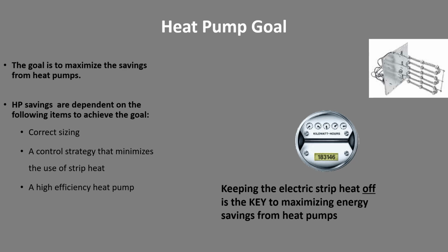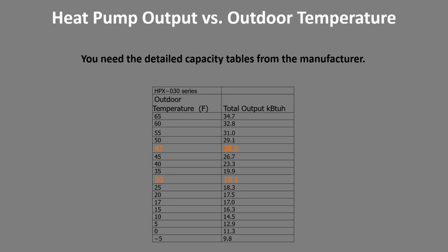The goal of installing heat pumps in the PTCS program is to keep the electric strip heat off. Let's just say we install a 3-ton heat pump with all the fans running. That heat pump's going to draw about 3 kW. Say we put in 15 kW worth of backup heat. As soon as that backup heat came on, it'd be 15 kW plus the 3 kW from the compressor and the fans. Boom, we got 18 kW worth of heat going onto that house. You basically increase the draw by a factor of 6. And that's when the meter starts to spin and the bills start to go up. The goal really is to minimize the amount of strip heat or auxiliary heat that the system has to use to maintain comfort in the house.